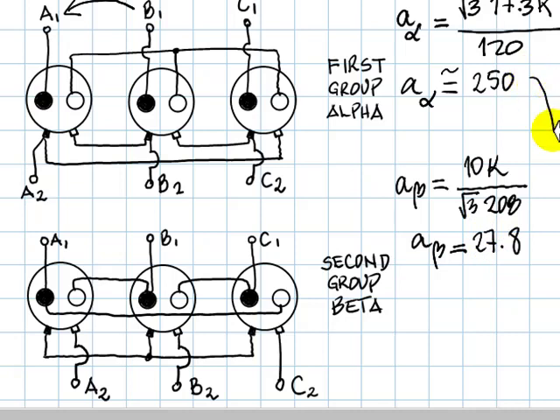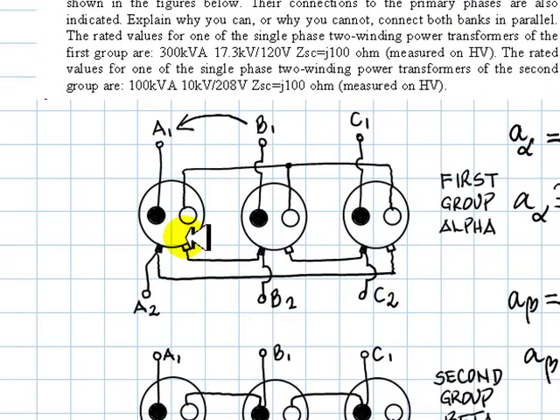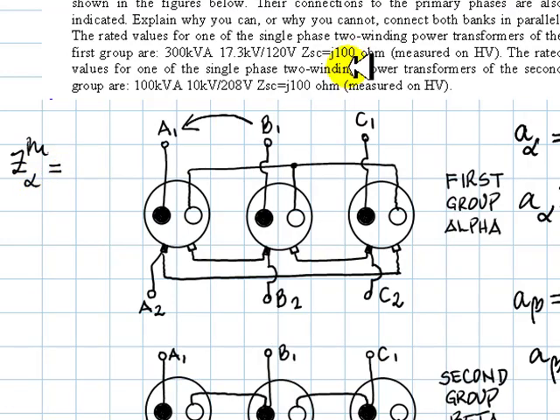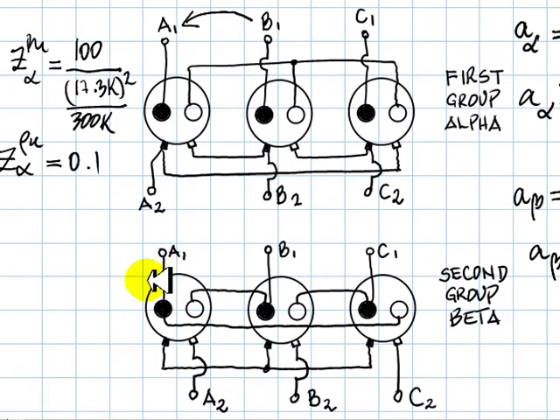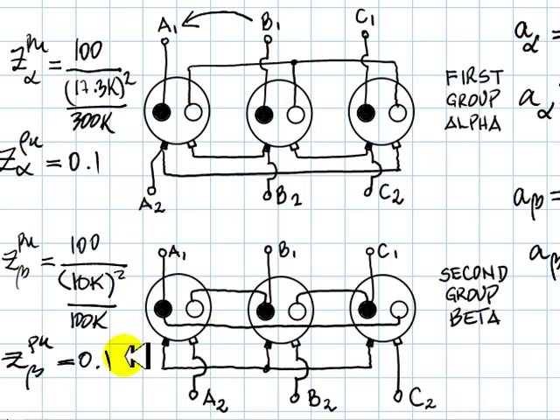They have different transformation ratios and should not be connected in parallel. However, let's also check the short-circuit impedances. The per-unit short-circuit impedance for Group Alpha is j100 divided by the base impedance on the high voltage side, giving 0.1 per unit. The per-unit short-circuit impedances of both banks turn out to be the same. The two banks meet two out of the three conditions to be connected in parallel, but these are AND conditions — if one is not met, they should not be connected in parallel.